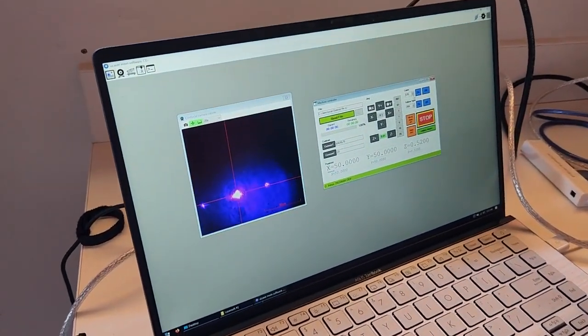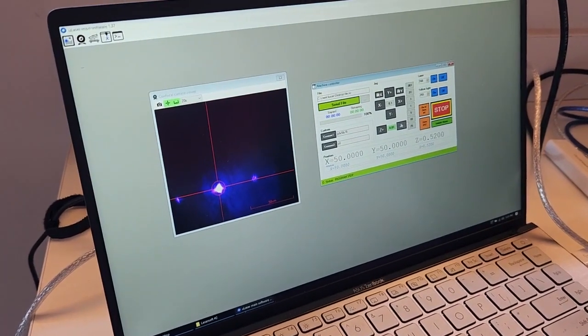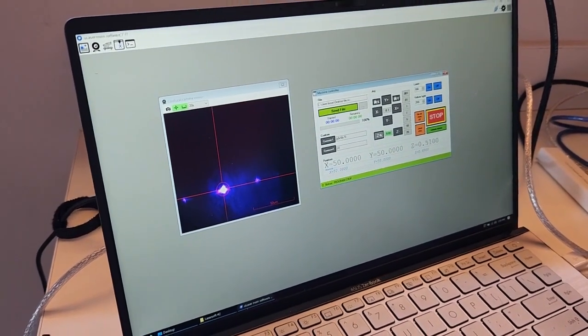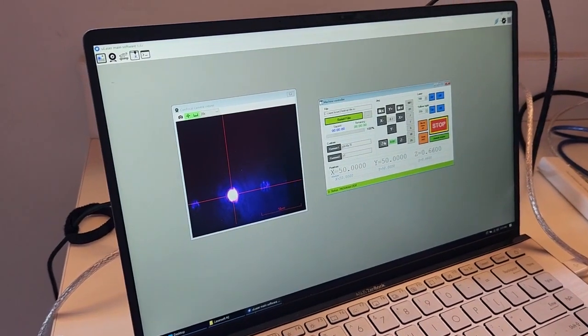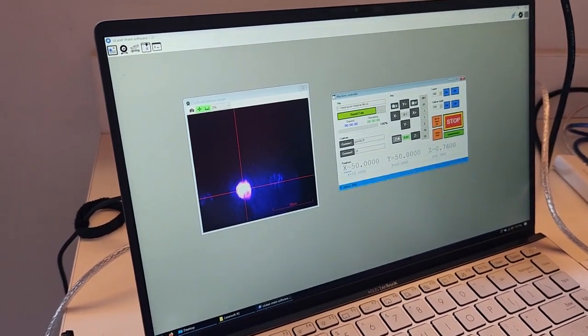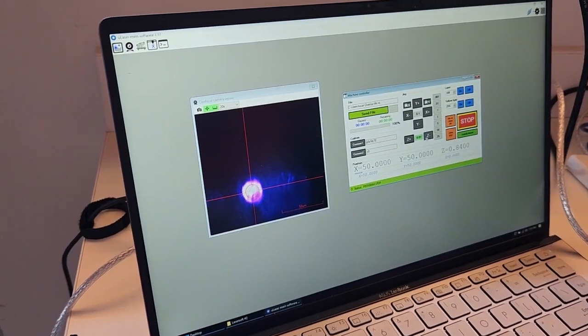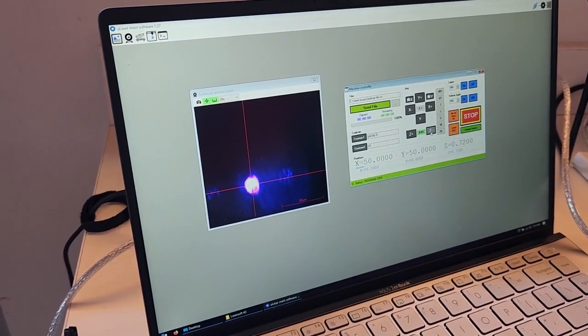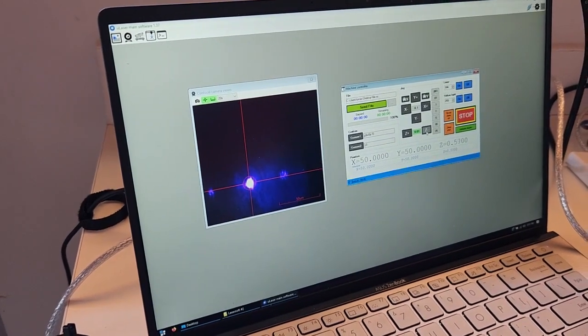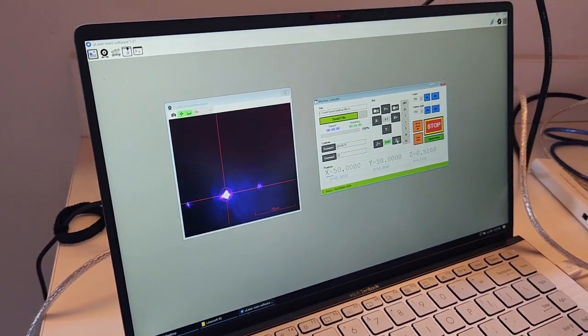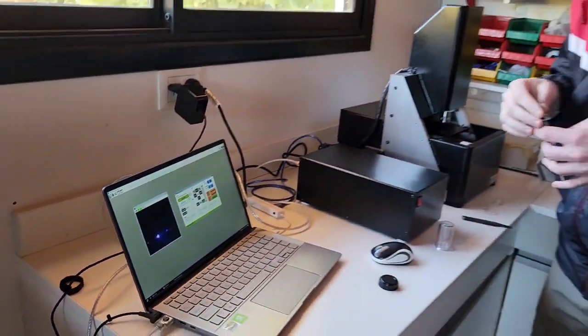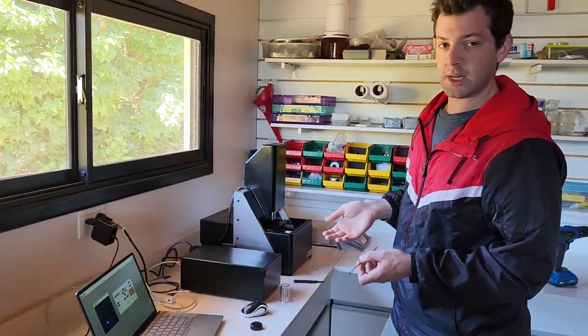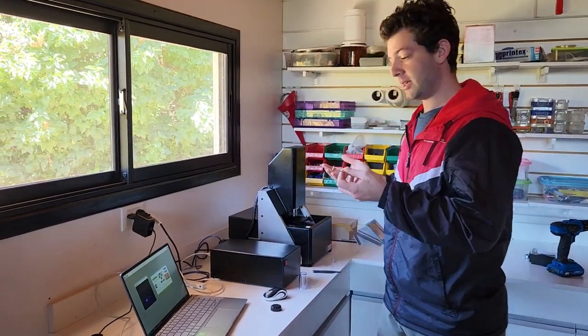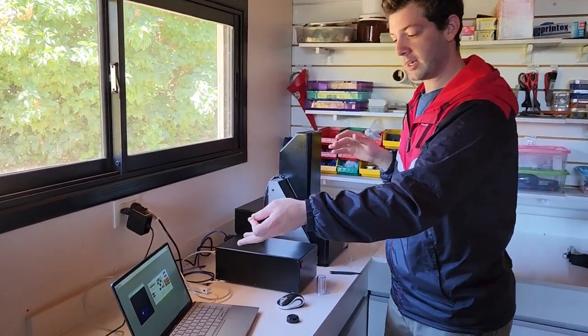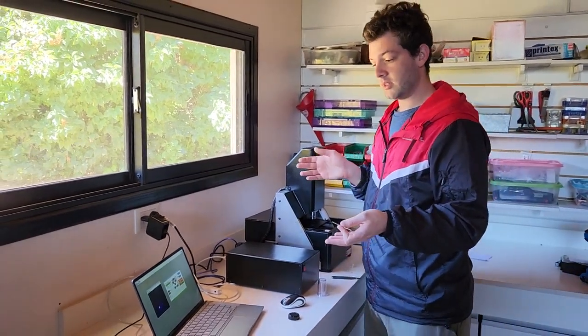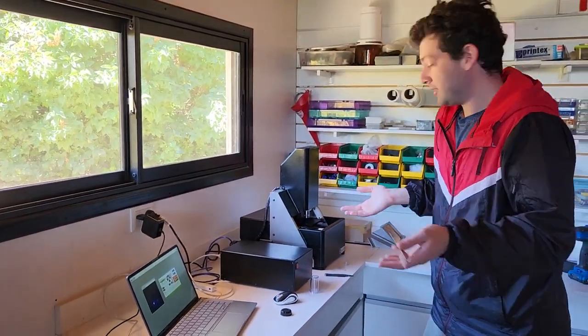We can even lower the brightness a bit so we can see the spot better. We can check the shape, that it grows in a more or less symmetrical way. This is what you are expected to see when it's aligned. And of course you need to make sure you are in a condition where you get the maximum brightness, okay? Because if it's not at maximum brightness, then it's not going to write anything. You need to make sure that when you align it, the brightness of the spot is basically the maximum. And basically that's it. Now it's aligned.